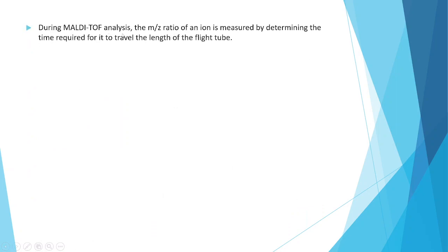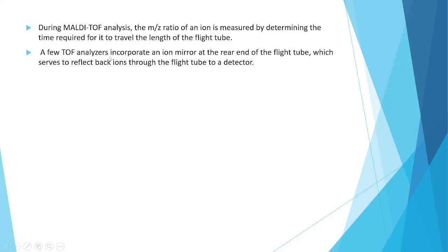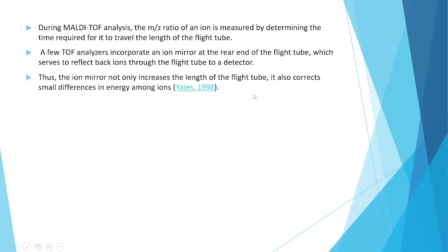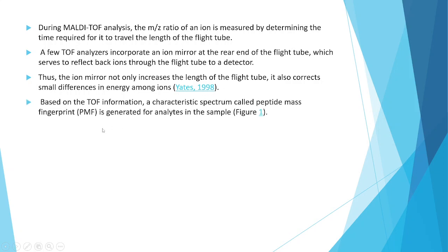During MALDI-TOF analysis, the m/z ratio of an ion is measured by determining the time required for it to travel the length of the flight tube. Some TOF analyzers incorporate an ion mirror at the rear end of the flight tube which serves to reflect back ions through the flight tube to the detector. The ion mirror not only increases the effective length of the flight tube but also corrects small differences in energy among ions, as described in 1998.